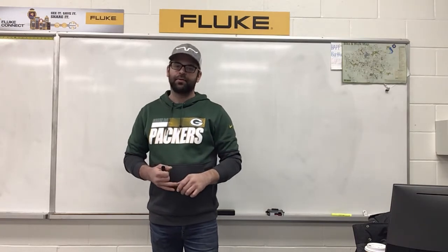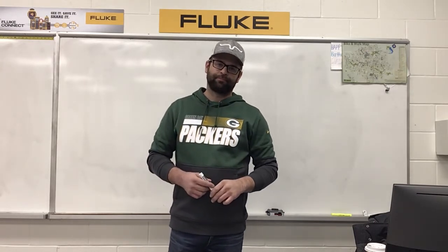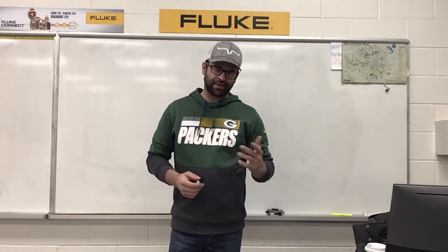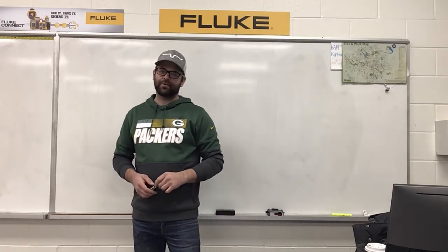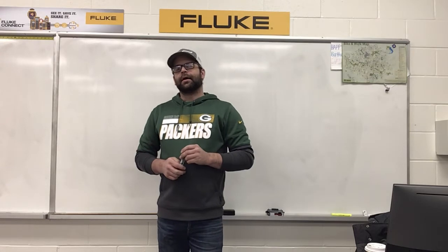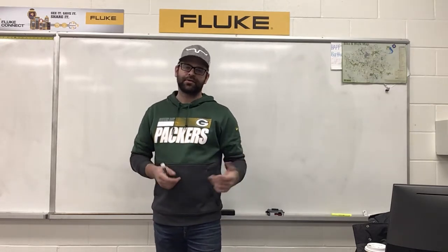So type T, TP, is blue, your type E being purple, EP, and the type J being white, and the type K being yellow. If you can know those, at least for construction, and also that the negative is red, other than for color code, that's the majority of the stuff you need to know for that. And then really know what the use of it is.